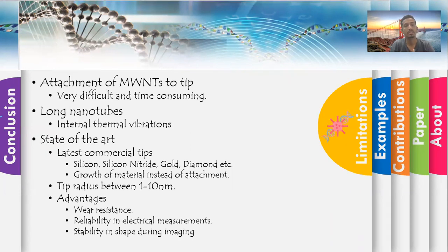There are some limitations to these nanotubes, because the attachment of these nanotubes to the tip is very difficult and time consuming. As they are long nanotubes, they have internal thermal vibrations due to which difficulties arise in atomic force microscopy imaging. If you look at the state-of-the-art materials used for tips, they are silicon, silicon nitride, gold, diamond, etc. Instead of attachment, what we do is we grow them on the tip by using the latest techniques.